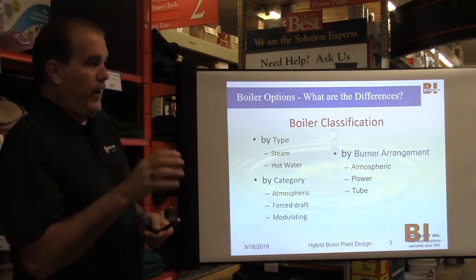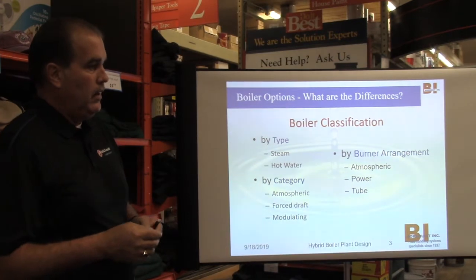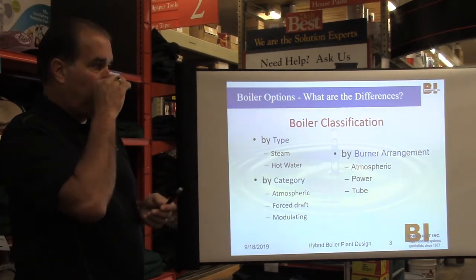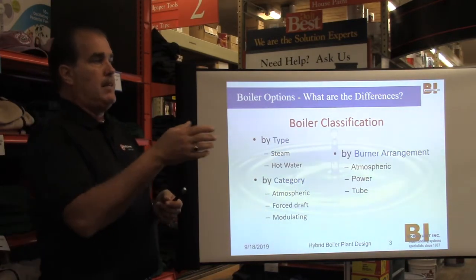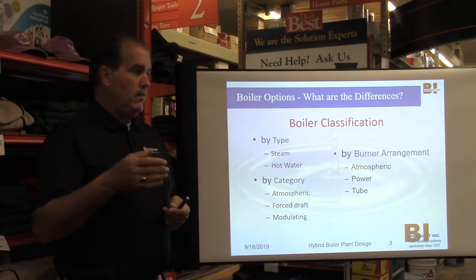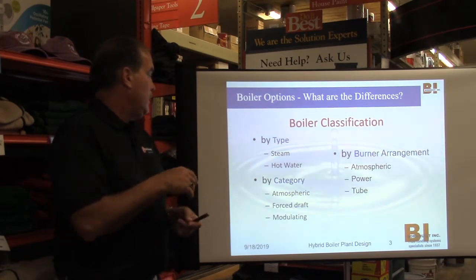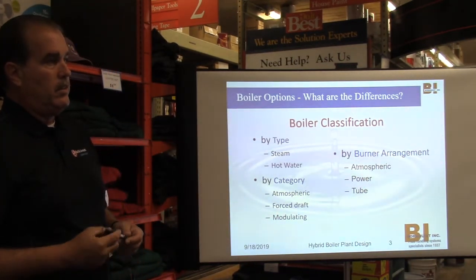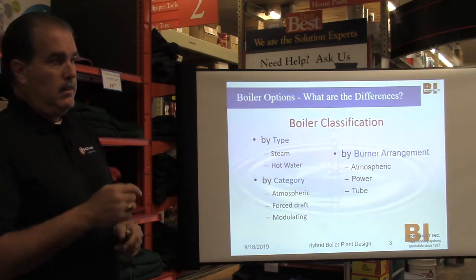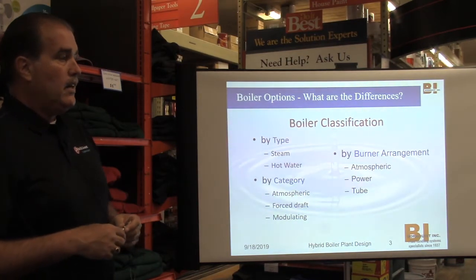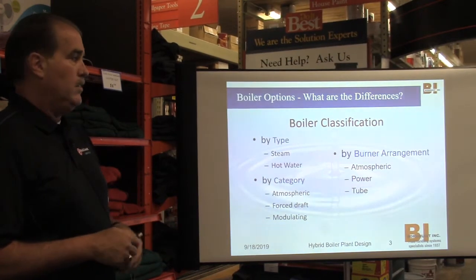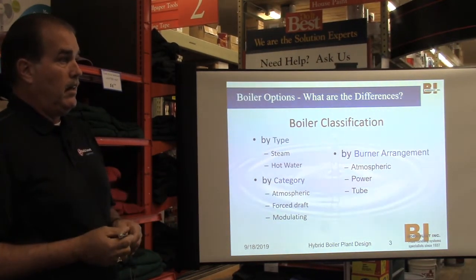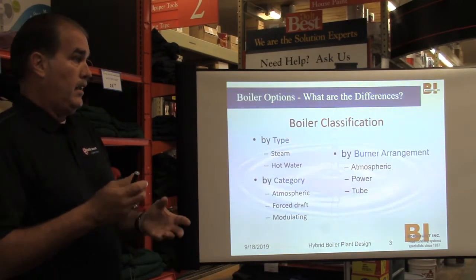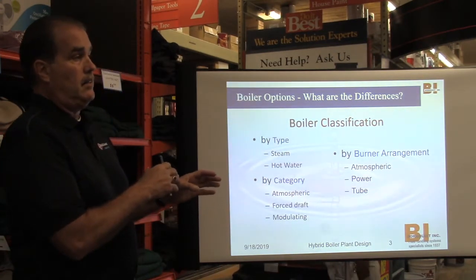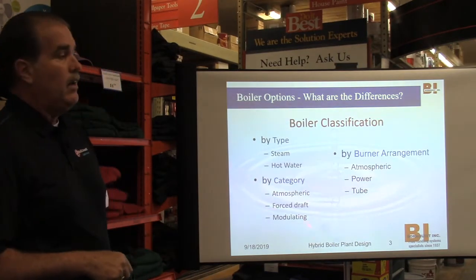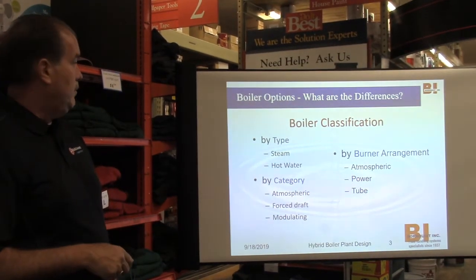Forced draft is there's actually a little fan in the boiler that's pushing the air through the boiler. But that means that usually you're going to have sealed piping, and that's where your boiler is a little more high efficient. That's where you might see that plastic PVC venting, or the smaller venting stainless steel, because these types of boilers are typically modulating. They're the ones that, when they say I'm installing a high efficiency type boiler, that's what they're talking about. It's not going to be your atmospheric, because your atmospheric is going to run right around 80% efficient, whereas a modulating hot water boiler can get well into the high 90s on efficiency. But with that, it's usually a condensing boiler, and I'm not going to get into that because that's not what we're really talking about here. But I'm just saying that's when they talk about high efficiency type boilers, that's what they're talking about.